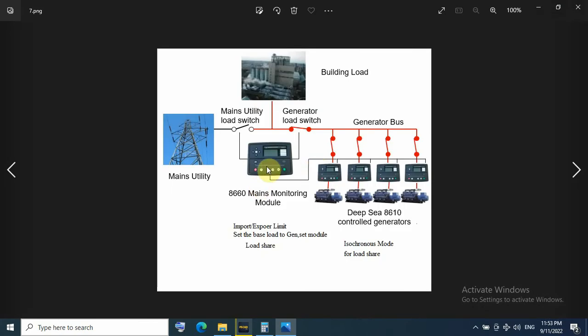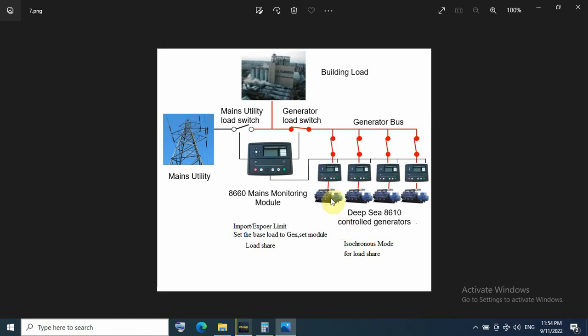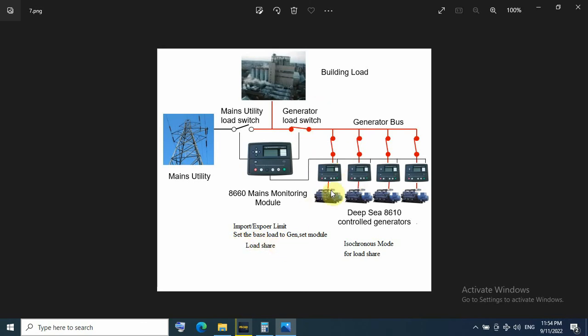If I take the DG module as example, for each genset I have synchronizing and load share module running in isochronous mode for load share. And for utility I will have mains module for monitoring and setting for import and export limit or to set the base load for generator module.